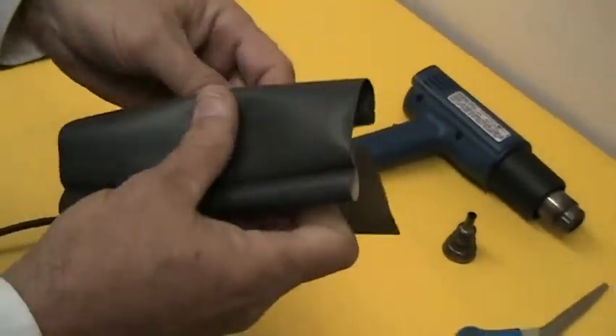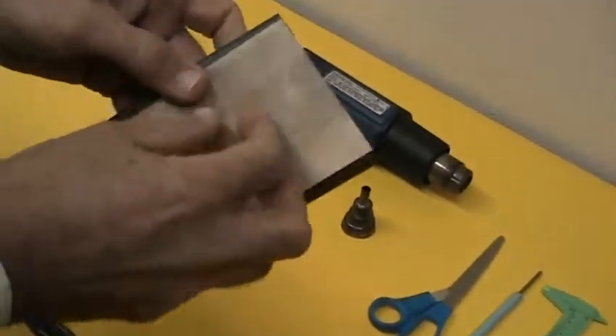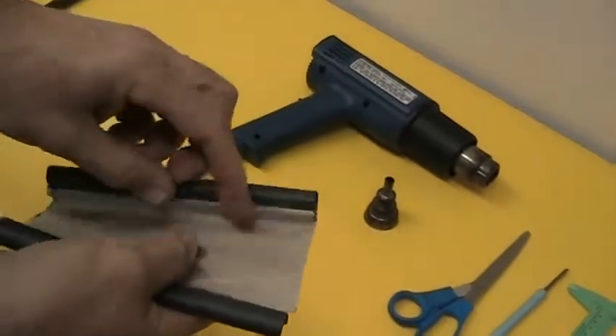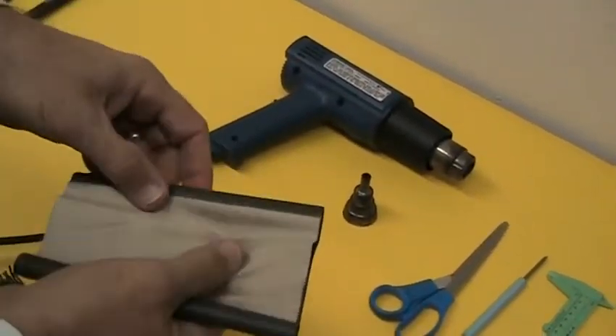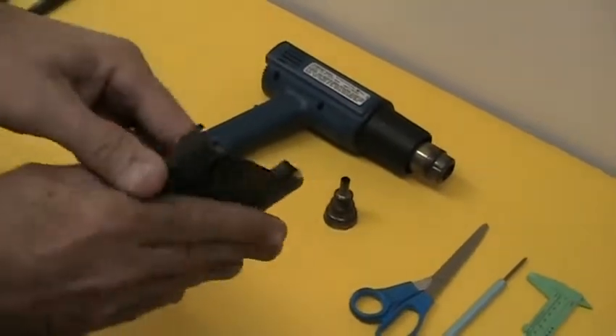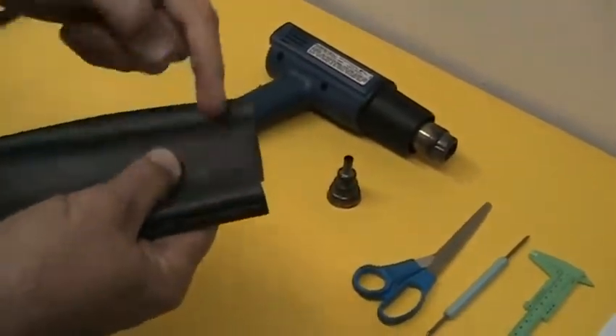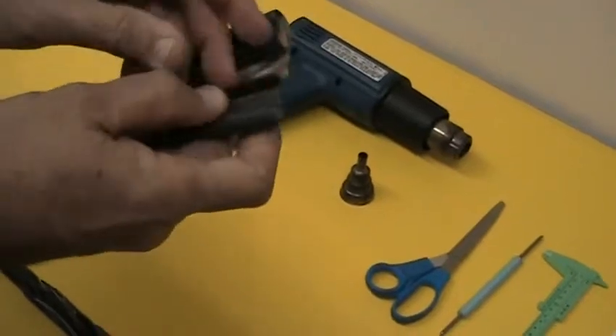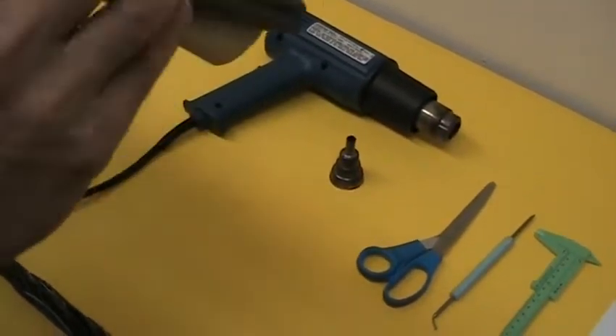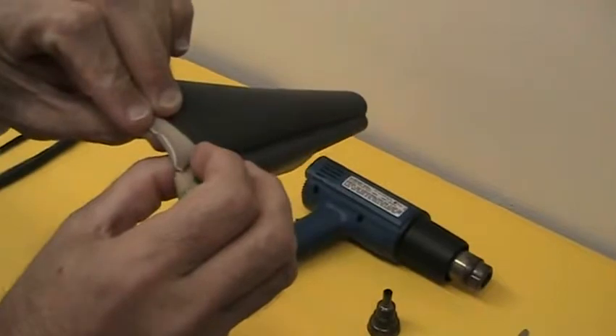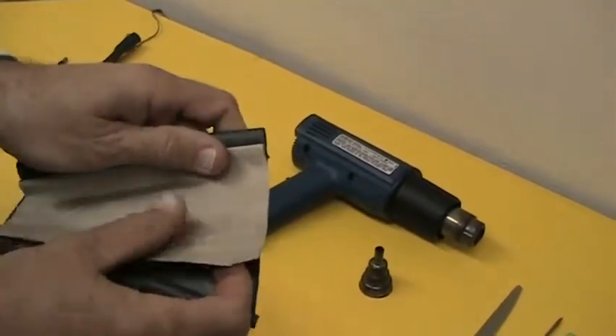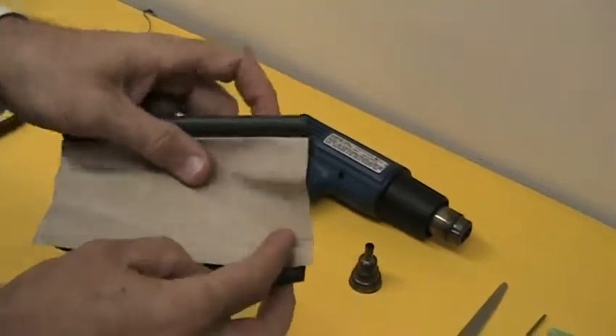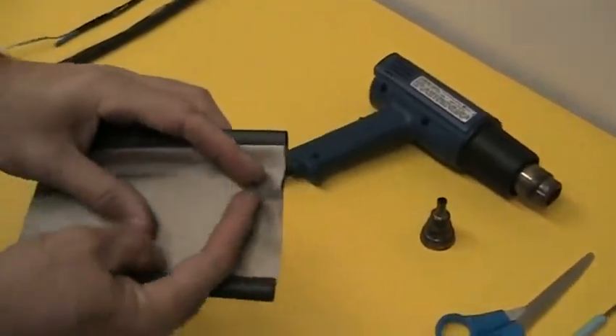It is also very possible to simply take the shield cloth and go up over the back of an electrical connector to make your ground contact or trim off a little of the excess heat shrink tubing and simply fold the shield back over the outside so you end up with the conductive surface on the outside at the end to accommodate a clamp device or something if you're going to carry the ground that way.